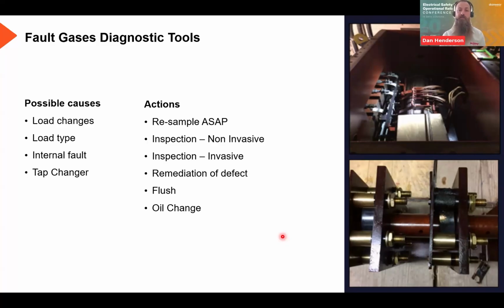Obviously, if you have got something happening in the transformer, as Ryan said, we can get an indication from the types of temperatures that can be expected, because of the types of gases that are in there, to try and pinpoint where it might be. But you can potentially do some non-invasive inspections, things like partial discharge surveys, to try and identify if you have got any internal issues and where they might be.